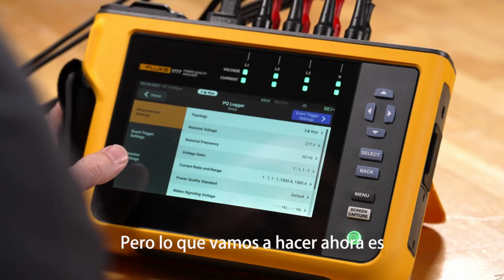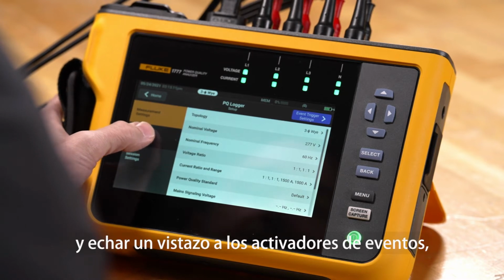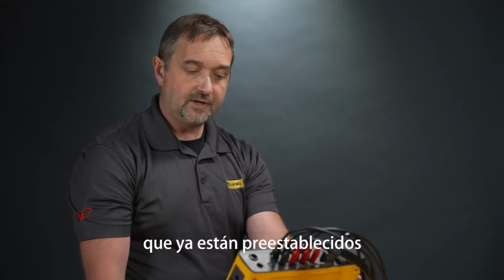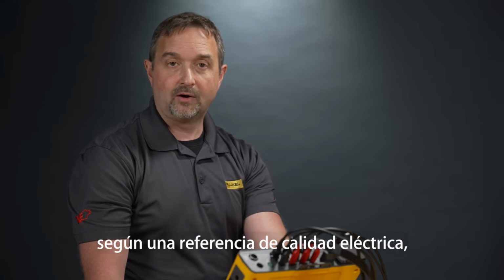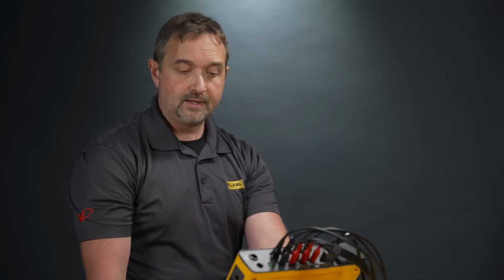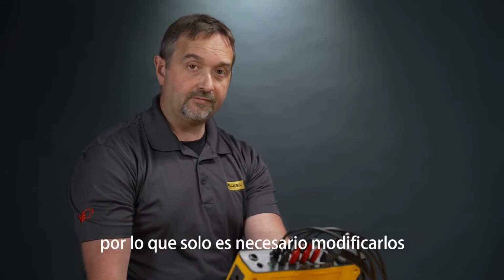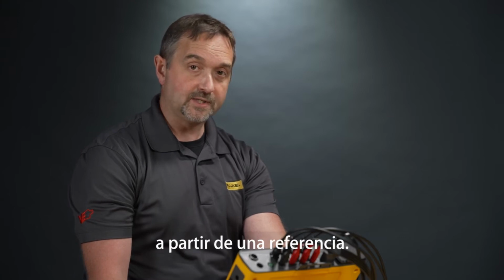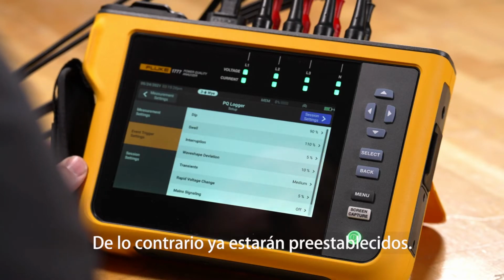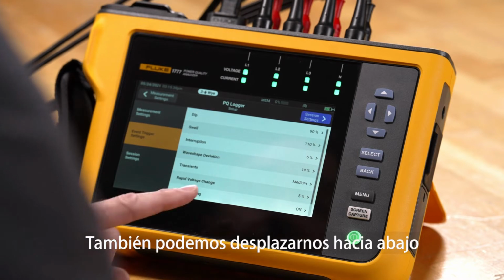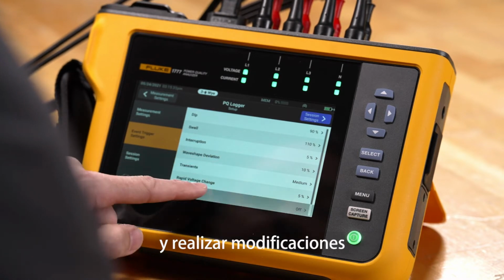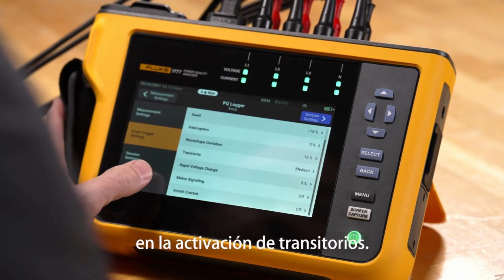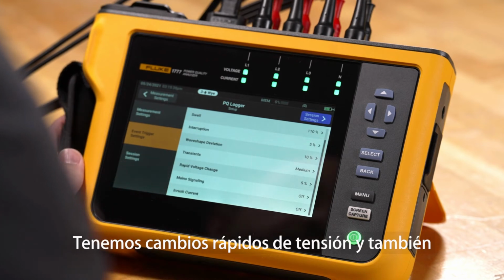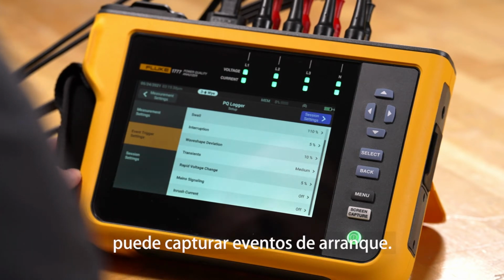But what we're going to do here is go down and take a look at our event triggers. Event triggers are already preset based on a power quality standard for you, so you don't actually need to modify these unless you want to make changes from a standard. We also have the ability to scroll down and make modifications to the transient triggering. We have rapid voltage changes as well as inrush capture.